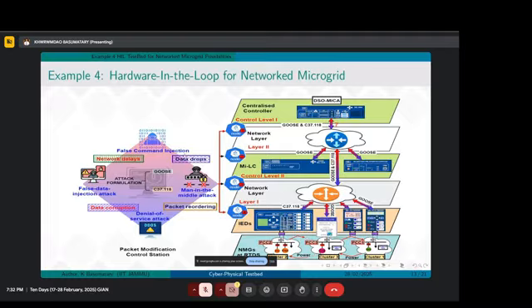Okay. And for example 4, we are also working on hardware in the loop for networked microgrids, where we have SEL RTACs and protection relays, 3 protection relays, and we have automation controllers. The purpose of doing this is that these 3 microgrids can work as a cluster during disconnection from the grid, and can be coordinated when one microgrid of the cluster is not getting enough power, then this microgrid has to borrow power from a neighbor. This kind of algorithm we have implemented in our present working testbeds. Our next task will be taking it forward by simulating different cyber threats.